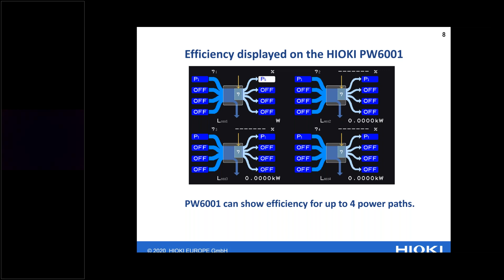So why is it happening that sometimes you will not get proper efficiency or you will not have the most accurate results? Well, that's basically because of a mathematical error. And that error is happening especially when the power factor is closer to 0. So the closer it becomes to 0, the smaller the power factor is, the more mathematical error you will get.